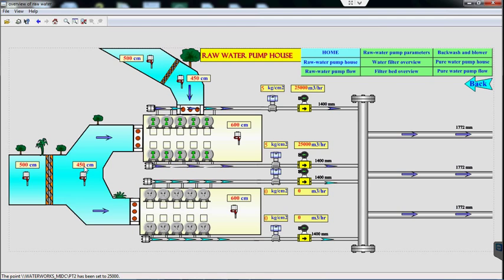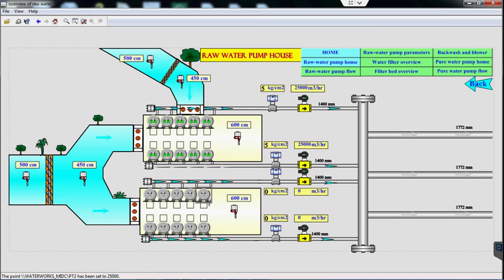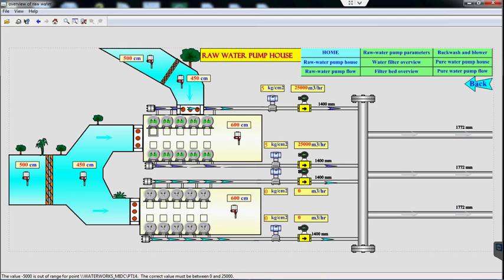Similarly, in case the inlet gate of the pump is choked, an alarm will be annunciated. Each pump house has a set of 10 pumps, and each pump can be operated from the control room. When the pump is started, pressure and flow are developed in the pipeline. If more pumps are started, more pressure and flow will be developed, which will be recorded by SCADA. A dedicated master PLC is designed to monitor and control the raw water pump house operations.